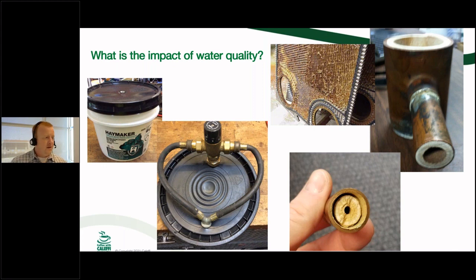That would be a perfect scenario to look into keeping a second mixing valve on site. Okay, and we've seen this done in many scenarios where it's, again, that mission critical application. They keep a second mixing valve on site. They do a hot swap once a year on a preventative maintenance schedule. So you're not working around this person who's frantic because they don't have hot water. You're working around a preventative maintenance schedule. They take out that mixing valve that was in there for a year, they clean it all out, and then they just leave it sit there and they wait until the next year and they do it again.